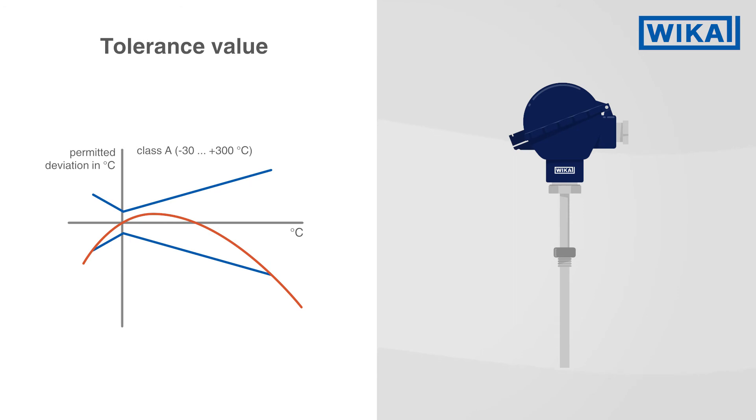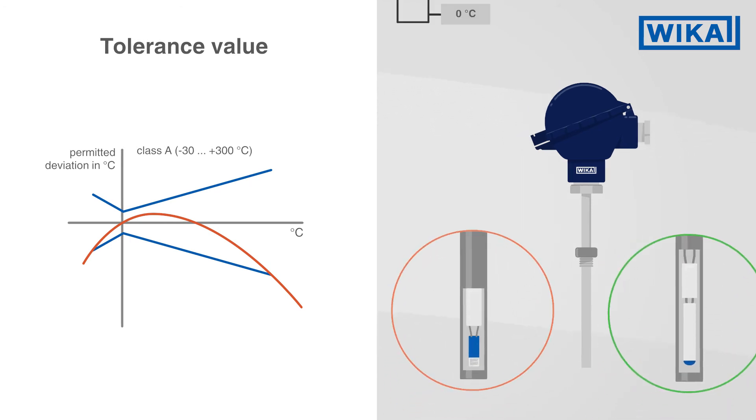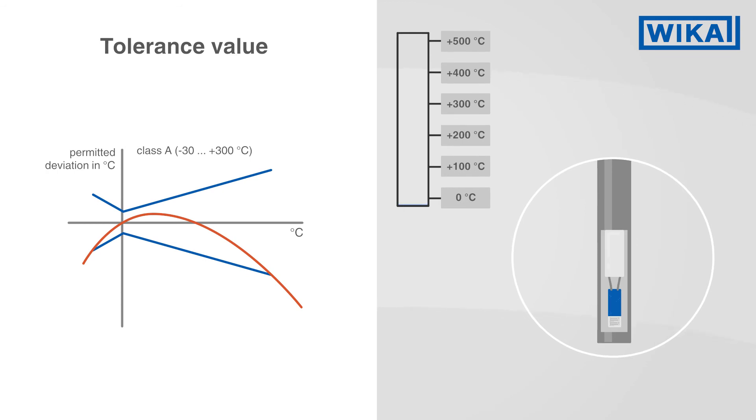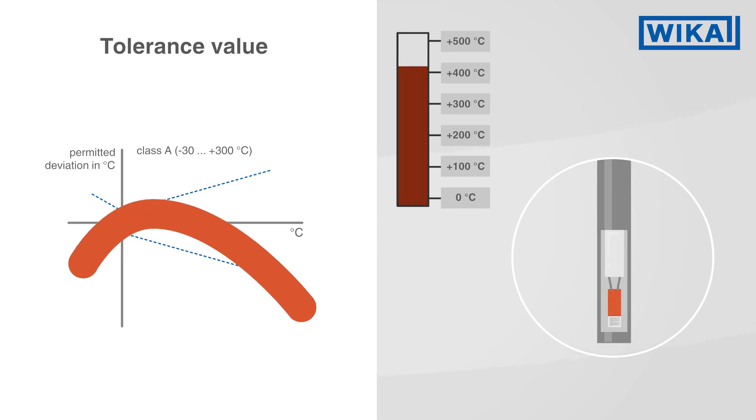This effect is more pronounced with thin film resistors than with wire wound sensors. If a resistance thermometer is used outside its measuring range, damage to the measuring resistor cannot be ruled out, and the accuracy of the measured value within its measuring range can no longer be guaranteed.